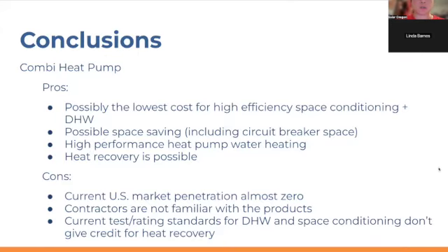Okay, we'll jump to the conclusions. Some of the pros and cons of combi systems: for a highly efficient space heating and domestic water heating system, it uses one compressor, and in the case of a refrigerant direct exchange system, you also have the minimal number of heat exchangers. So very likely you'll end up with the lowest cost system to achieve high efficiency space heating and domestic hot water.